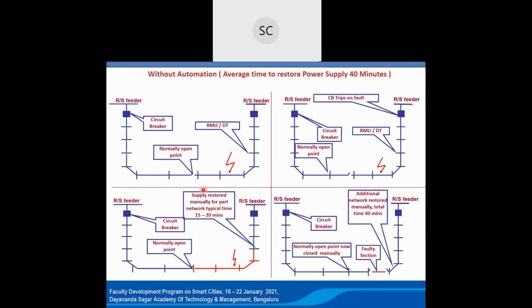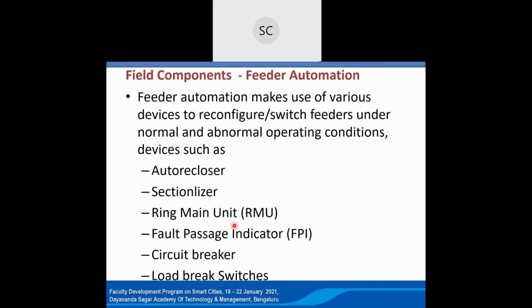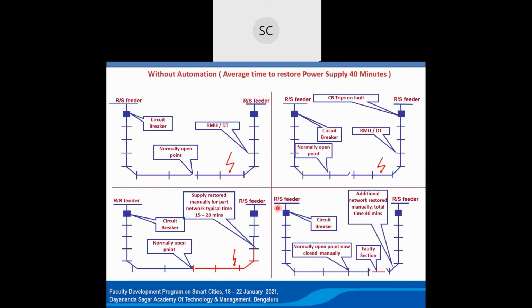Let us assume a fault happens here. The circuit trips on the fault. You can see the complete area has an outage because the breaker tripped on this side. Then the lineman has to come and manually close the switch. And this is the faulty area. By the time the crew comes and isolates all this, it will take more than 40 minutes, and this many customers are affected, while only the faulty area should have limited customers. It is all a manual system, how we are doing it.